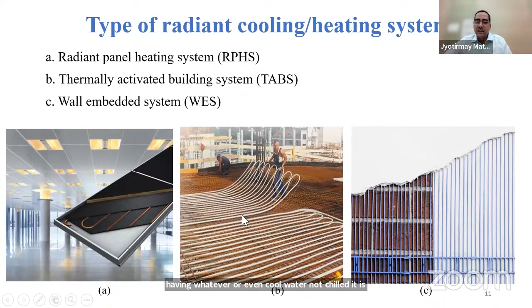What they do is basically have active integration of active and passive systems. Now what you can do is have a chiller, but if you're getting sufficiently cool water from geothermal, through the earth air tunnel, I can directly circulate that water through the pipe and get my heat absorbed. If I don't have an earth air tunnel, I can use evaporative cooling, meaning my cooling tower.